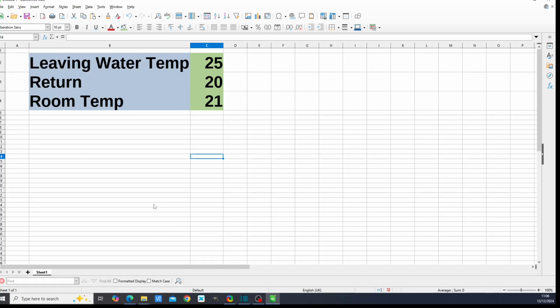So when it comes to weather dependent set points, the warmer your ambient air temperature, the lower your leaving water temperature. My leaving water temperature is set to 25 degrees Celsius. And ideally, you want to have a temperature gradient of 5 degrees between your leaving water and your return temperature. But you can see the problem here. This return temperature is thermodynamically impossible when your room temperature is 21 degrees. You cannot have a return temperature that is colder than your room temperature. So what happens actually is that your return temperature is probably 23.5 degrees Celsius. At that point, you've only got a temperature gradient of 1.5 degrees.